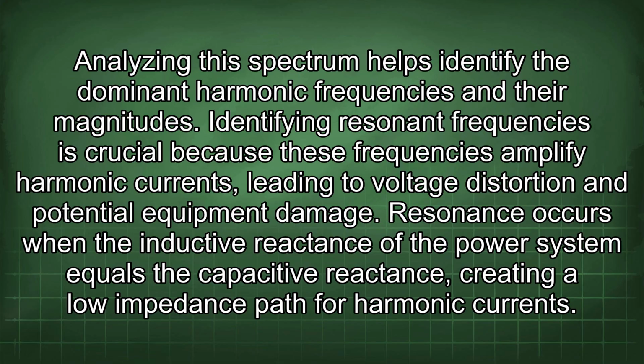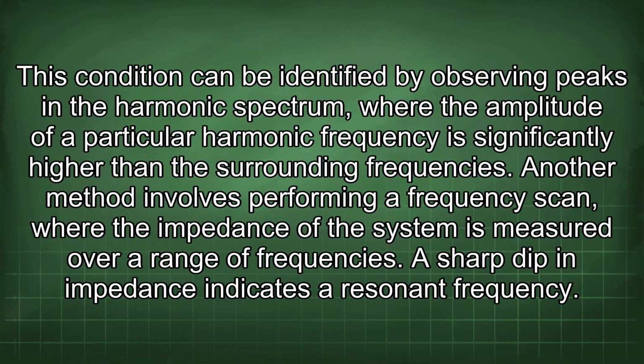Resonance occurs when the inductive reactance of the power system equals the capacitive reactance, creating a low impedance path for harmonic currents. This condition can be identified by observing peaks in the harmonic spectrum, where the amplitude of a particular harmonic frequency is significantly higher than the surrounding frequencies. Another method involves performing a frequency scan, where the impedance of the system is measured over a range of frequencies. A sharp dip in impedance indicates a resonant frequency.